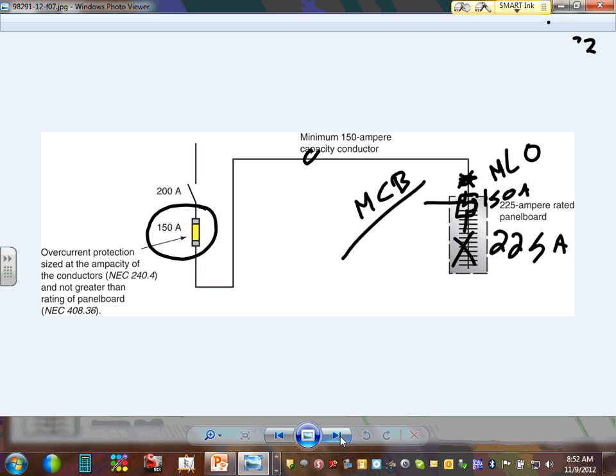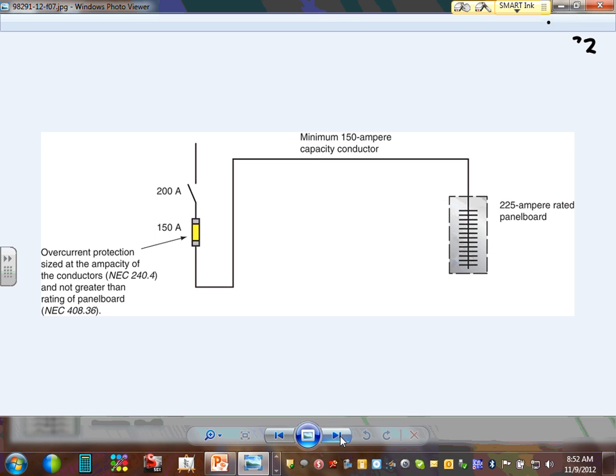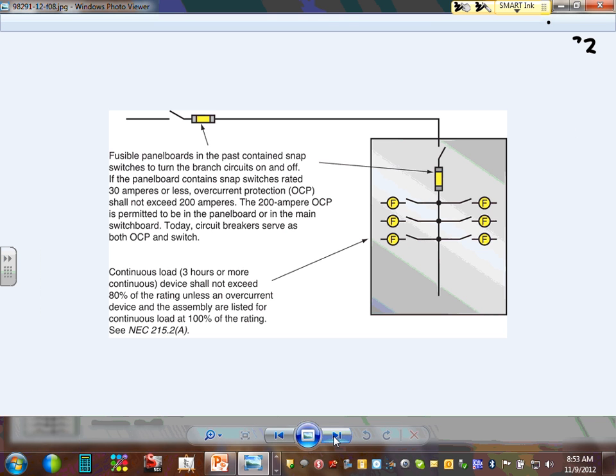Okay. So that's basically the circuit breaker. Here's the second option. Can you guys see that? The second option is to have two circuit breakers. In this case, I have 200 amps, 200 amps. Each one of these is 200 amps. Fusible panel. So I have 200 amp here and 200 amp here.